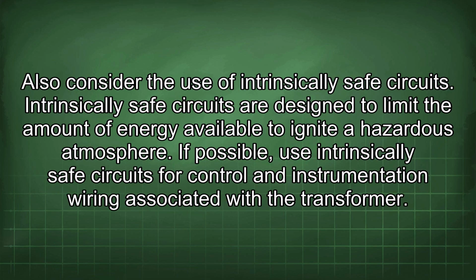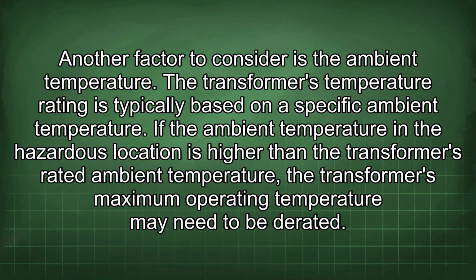Also consider the use of intrinsically safe circuits. Intrinsically safe circuits are designed to limit the amount of energy available to ignite a hazardous atmosphere. If possible, use intrinsically safe circuits for control and instrumentation wiring associated with the transformer. Another factor to consider is the ambient temperature. The transformer's temperature rating is typically based on a specific ambient temperature. If the ambient temperature in the hazardous location is higher than the transformer's rated ambient temperature, the transformer's maximum operating temperature may need to be derated.